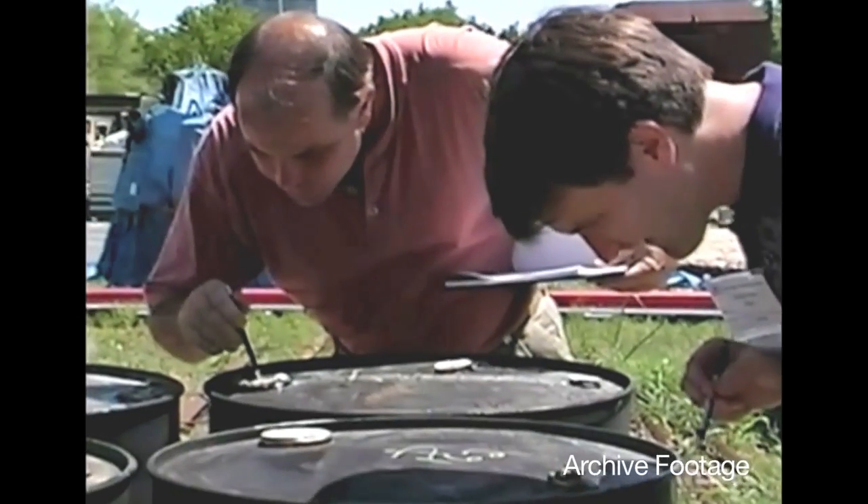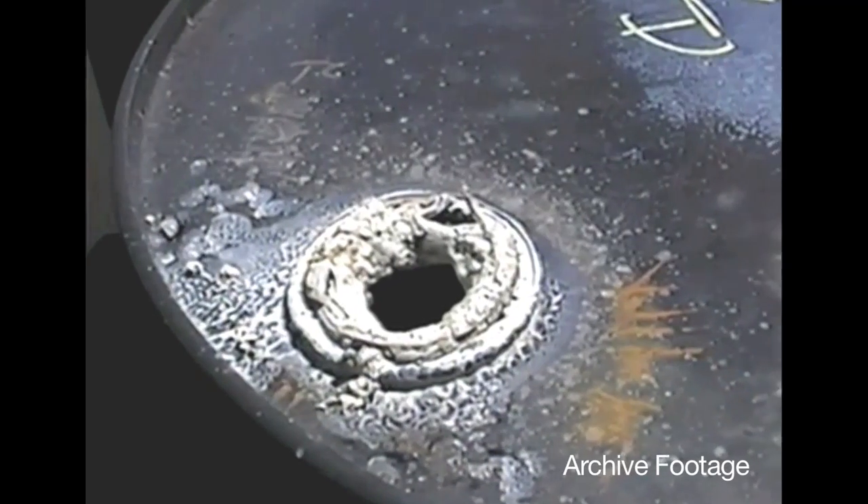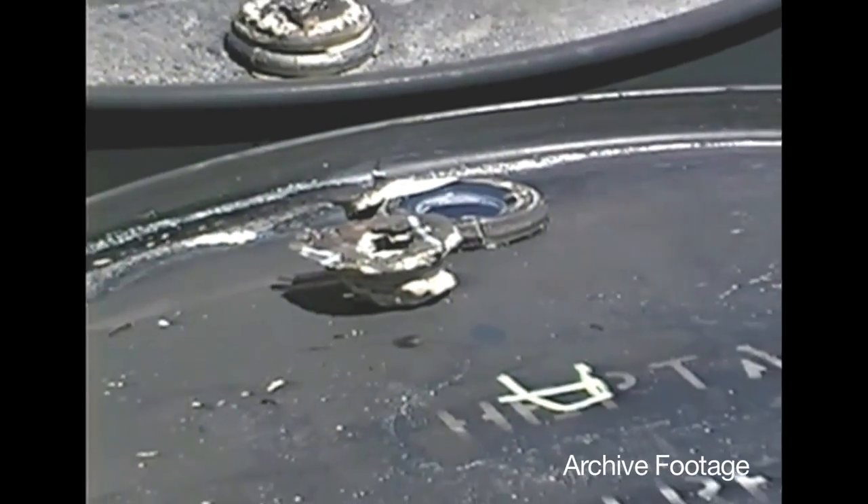The main value of a steel drum is that we can protect it. If I put a liquid that will burn inside a steel drum and provide adequate cooling with sprinklers, I end up with a scenario where I might only be looking at a drum or two that were involved in an accident, while the remaining drums exposed to fire don't fail.